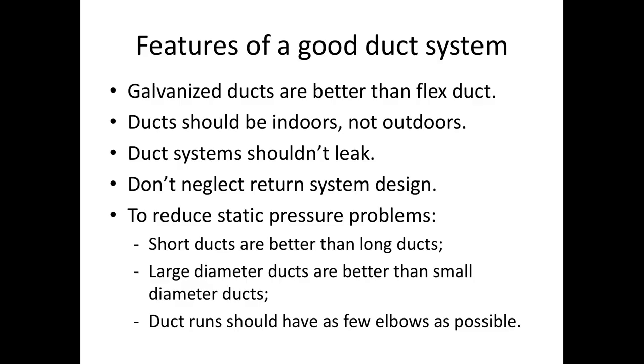So we end up with systems with ducts in a lot of cases. You may be building a house with a conventional furnace, or you may be having a ducted mini split system. A lot of duct systems are poorly installed. These are the basics: galvanized ducts are better than flex ducts. Ducts should be indoors, not outdoors, so you don't want them in a ventilated crawl space or an attic. Duct systems shouldn't leak. It sounds obvious, just like plumbing systems, but most of them do, so they should be tested with a duct blaster.